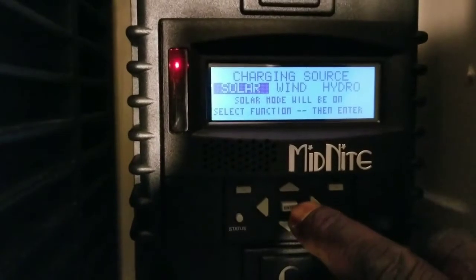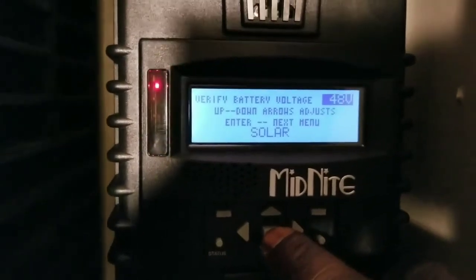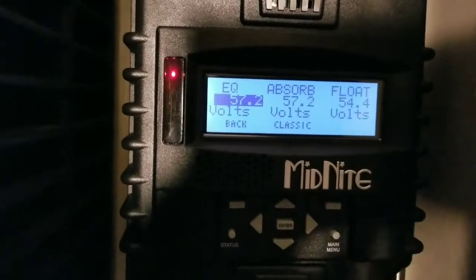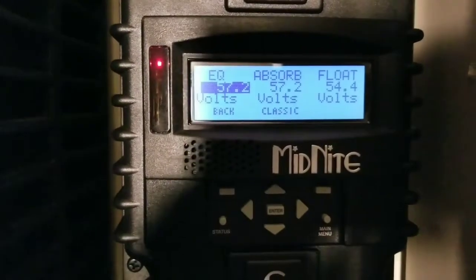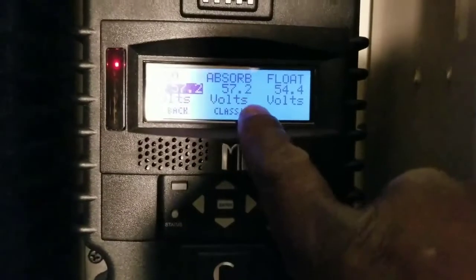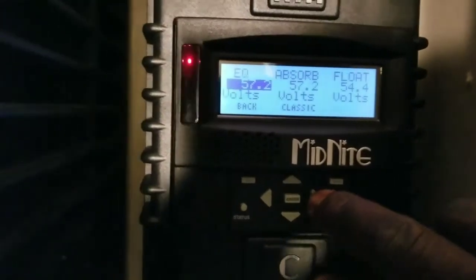We push the center button and it's gonna tell us 48 volts because it automatically configures that according to your battery bank. We press enter and it's telling us right now: equalize 57.2, absorb 57.2, float 54.4 - so it's thinking AGM. The EQ and the absorb are the same, so we're gonna be changing that.